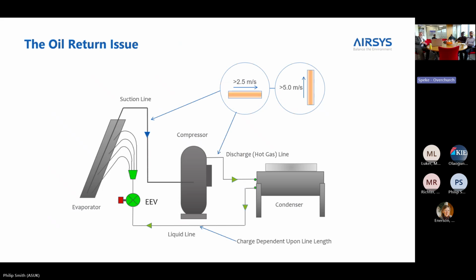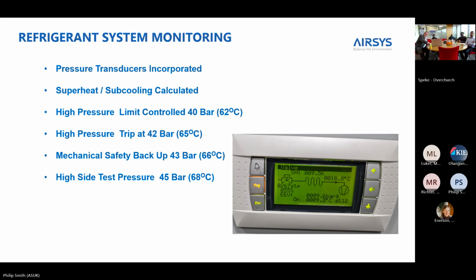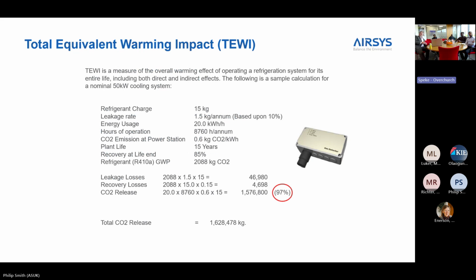The final issue with all refrigerant products, again, which is something to factor in, is they require oil, and they require that oil to be recirculated in order to protect the compressor, which requires minimum velocities around the system. And we then monitor the pressures that the systems work at to make sure that they're okay, which is great.